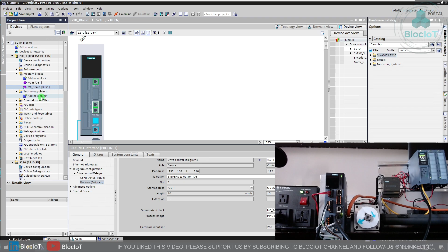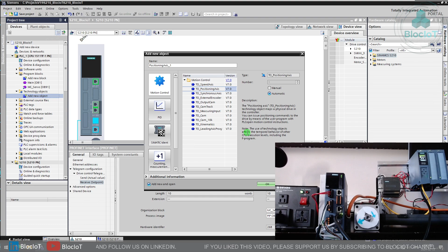So the first thing that you need to do is go under the technology objects and add a new object. As you may be familiar with Siemens PLCs, technology objects are objects that do different things. One of the main objects is motion control. And of course, you can use PID control also. That's another technology object. But for this demo, we go with motion control. And you have different options. Based on the application, you might select the synchronous axis. If you have an external encoder, you might want to do cams and measurement inputs. But for this demo, we just want to control the position of the shaft based on some commands that we send from the PLC. So we just select the technology object, positioning axis. You can give it your own name, but I just leave it as default and I hit OK.